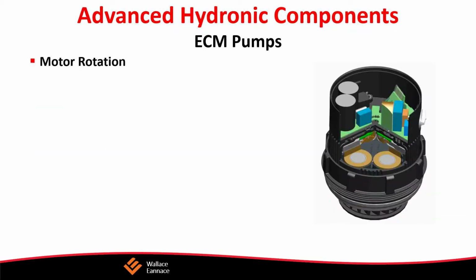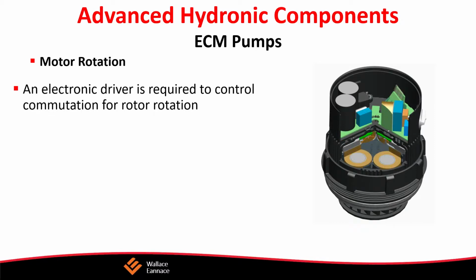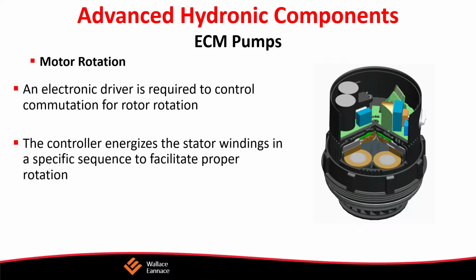So let's talk about some of the newer pumping options. And primary to that is electronically commutated motor pumps, ECM pumps. Now, the difference is with these pumps, they use permanent magnets. There's no shaft, no seals or bushings, and there's only one moving part. So here you see an ECM pump. You have the volute, you have a magnetically centered spherical impeller or rotor, a stepless speed motor, and a high efficiency ECM motor.